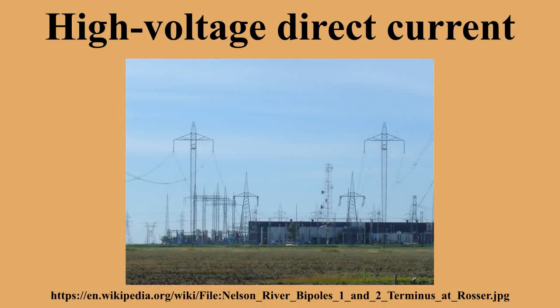High-voltage DC circuit breaker. HVDC circuit breakers are difficult to build because some mechanism must be included in the circuit breaker to force current to zero. Otherwise, arcing and contact wear would be too great to allow reliable switching. In November 2012, ABB announced development of the world's first HVDC circuit breaker. The ABB breaker contains 4 switching elements, 2 mechanical and 2 semiconductor. Normally, power flows through the low-speed mechanical switch, the high-speed mechanical switch, and the low-voltage semiconductor switch. The last 2 switches are paralleled by the high-voltage semiconductor switch.